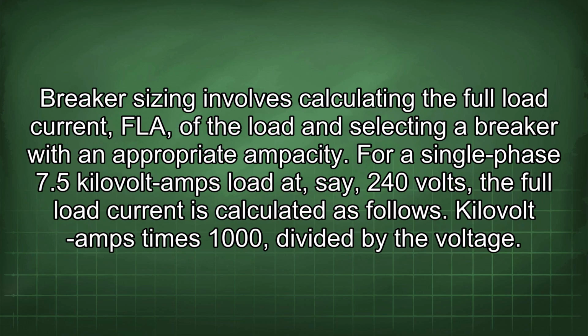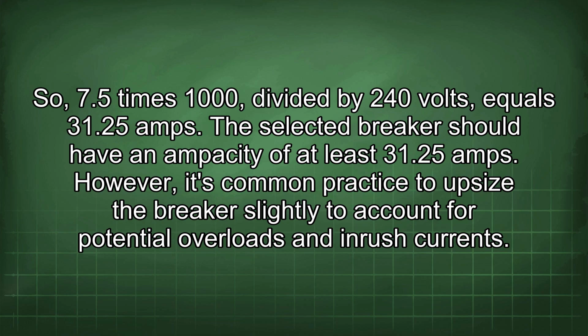Breaker sizing involves calculating the full load current, FLA of the load and selecting a breaker with an appropriate ampacity. For a single-phase 7.5 kVA load at, say, 240 volts, the full load current is calculated as follows: kilovolt-amps times 1000 divided by the voltage. So, 7.5 times 1000 divided by 240 volts equals 31.25 amps. The selected breaker should have an ampacity of at least 31.25 amps.